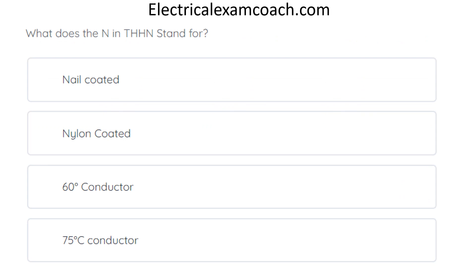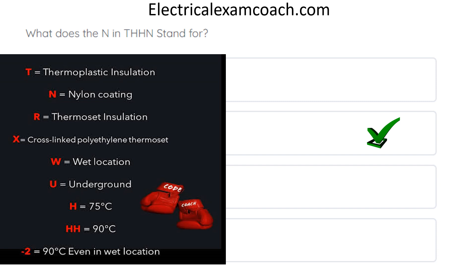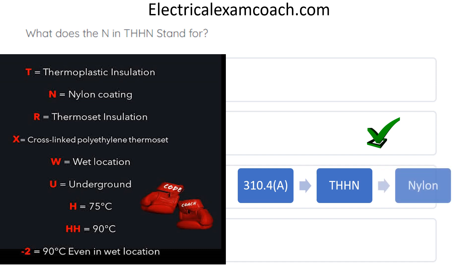What does the N in THHN stand for? The correct answer is nylon coated. There's a reference picture available at electricalcodecoach.com under free resources that breaks all of this down. Make a tab for Table 310.4(A) — if you're allowed tabs in your state. Head to that table, find THHN, and you'll find it is equivalent to nylon coating. You'll also learn about all the different wire types and their temperature ratings — 75, 90 degrees, and so forth.